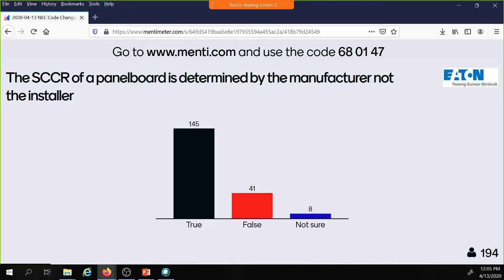We're going to review some of the labels on the equipment. So depending upon how you take this one, I'm sure that a lot of people, when I say panel board, are picturing an enclosed panel board with breakers installed. But some of that 145 may be thinking of that panel board just inside the box without any overcurrent devices. In any case, I would vote for false if it was me. But again, it's all in perspective on where your head was at when you hit that true button. We will go through so you completely understand the perspective of the short circuit current rating of a panel board and switchboard, especially those two, because as a manufacturer we publish the recipe, but it's up to the installer to determine the short circuit current rating as it is installed.